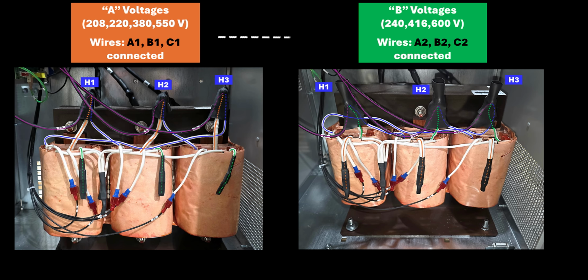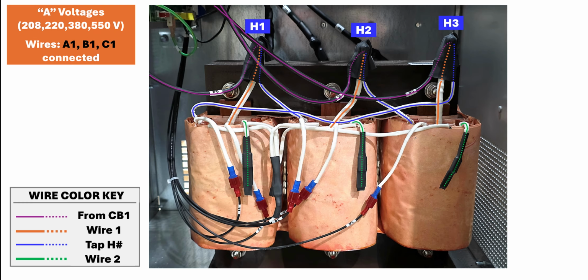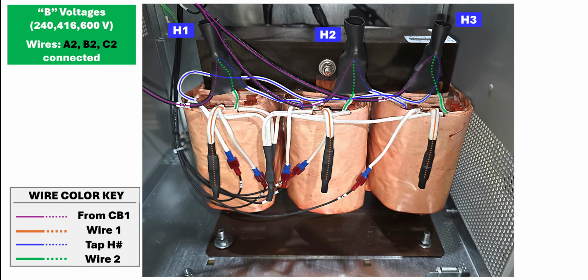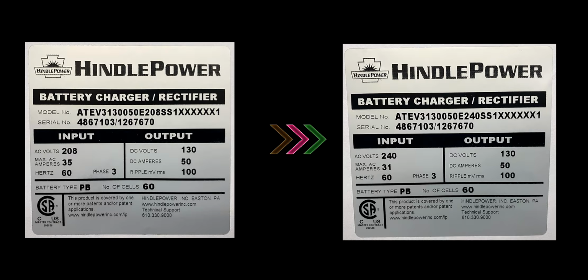All right, we've finished demonstrating how to change from 208 volts to 240 volts on an ATevo 3-phase charger with a dual input voltage design. To summarize, we've simply swapped wires on all 3 transformer coils that connect to the primary taps and their corresponding wires to the AC circuit breaker. After rewiring your charger, it is wise to properly label it with its new AC input voltage. Contact HindlePower for a new nameplate to replace the nameplate that shows the voltage it had prior to your conversion.